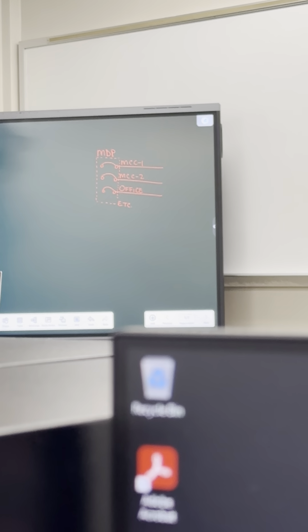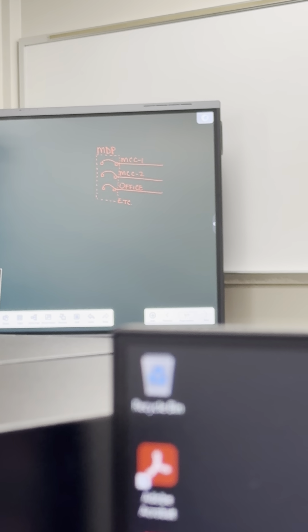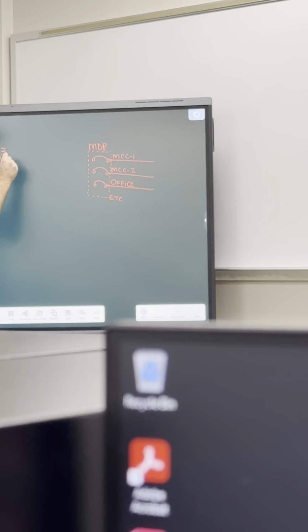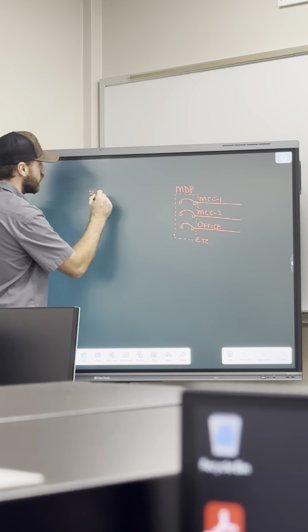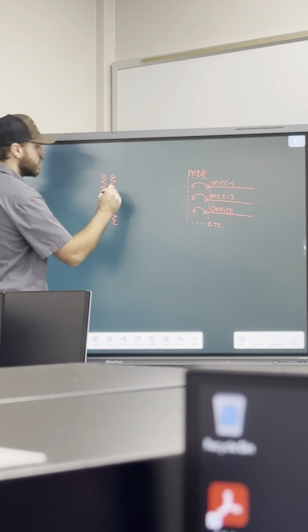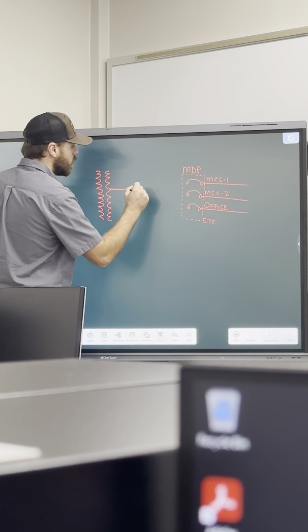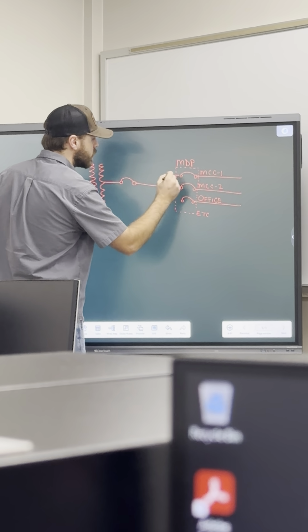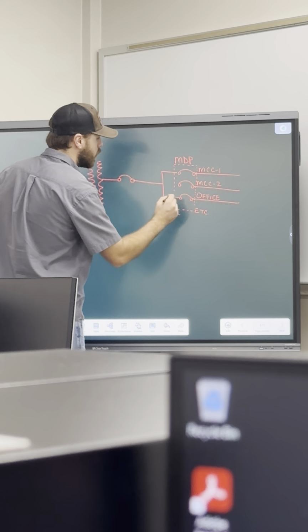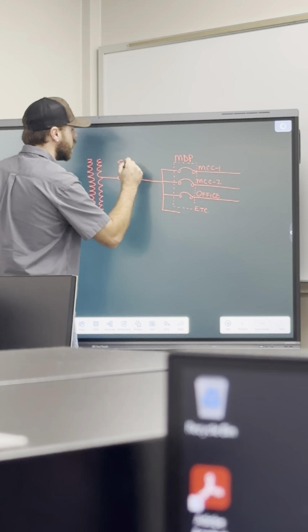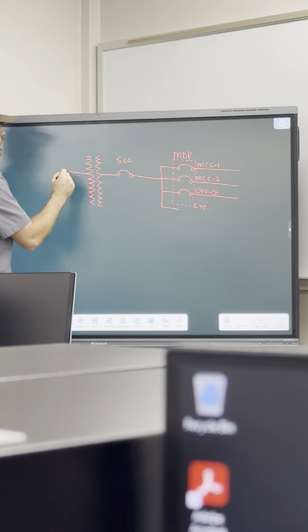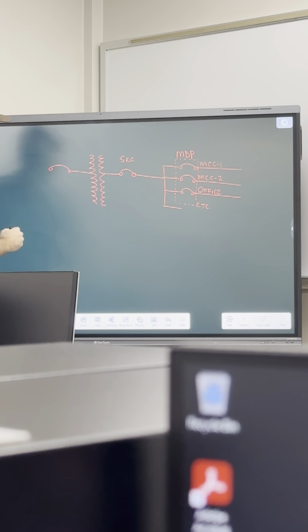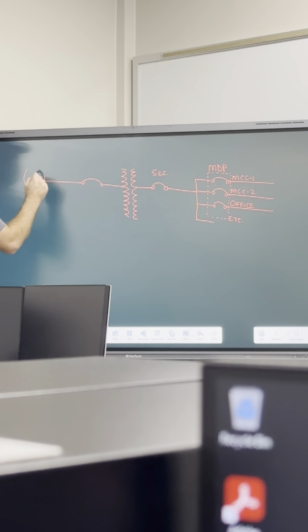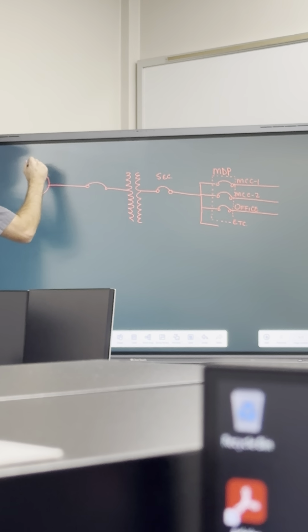So we know that this is going out and feeding everything in our shop, but what is feeding this main distribution panel? That's what we're going to focus on today, and that's going to be our substation. Our substation is going to be made up of a transformer. We will have a secondary breaker on this one. We'll also have a primary breaker. And then we have our source, which is the utility in this case.